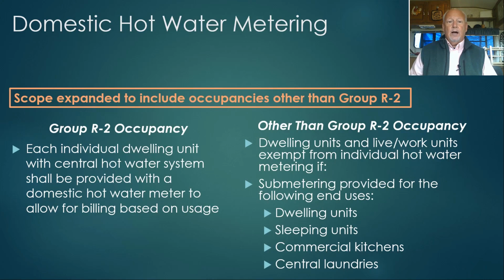They're exempt from individual hot water metering if you provide sub-metering for the following end uses. So dwelling units, sleeping units, commercial kitchens, and central laundry. So if you do have dwelling units in occupancies other than Group R2, you need to provide sub-metering for those dwelling units, but it doesn't have to be each individual dwelling unit. So if you had, for example, sleeping units in a fire station, and they had individual restrooms, for example, or even dwelling units in a fire station, you would just need to sub-meter the hot water supply to that group of dwelling units. You would not have to sub-meter each individual dwelling unit.